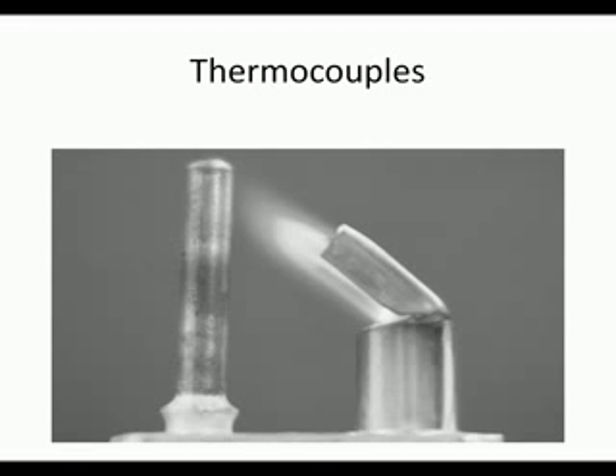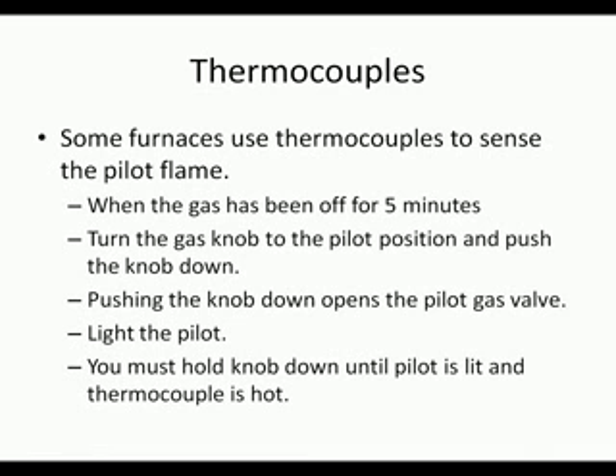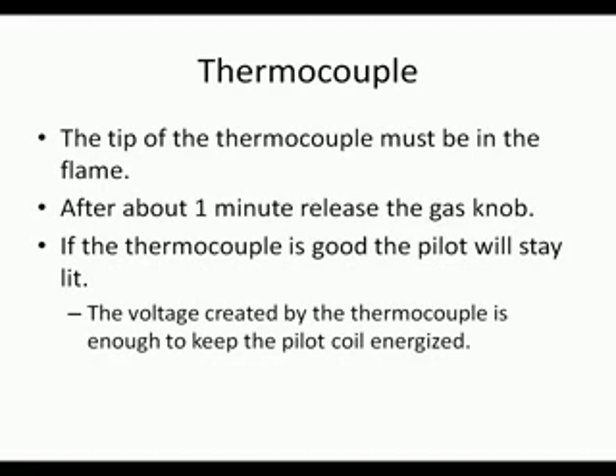This is an example of a thermocouple. A thermocouple has hot junctions and cold junctions. The difference between the two creates the voltage, which will power a load. Thermocouples sit in the pilot flame. They heat up on the tip and they're cooled down at the bottom, providing the hot and cold junction. Some furnaces use thermocouples to sense the pilot flame.